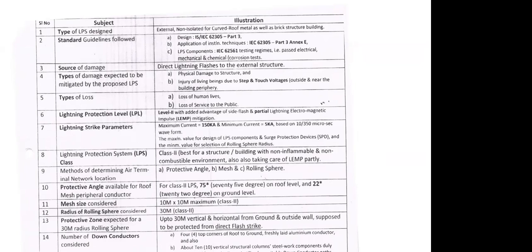Now, the method of determining air terminal network location: protective angle, mesh, and rolling sphere. This is what I said, that this protective angle is very important, because in which direction lightning will hit, nobody knows, whatever design, whatever research we do. Protective angle available for roof mesh peripheral conductor for class 2 LPS is 75 degrees on roof level and 22 degrees on ground level. This is how we place the terminals or the ground conductors.